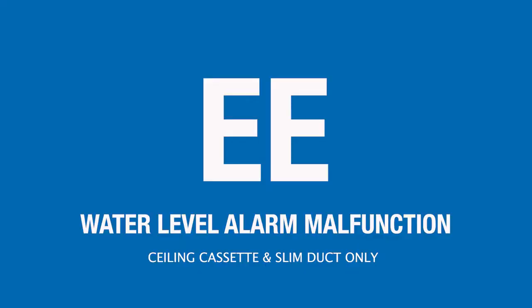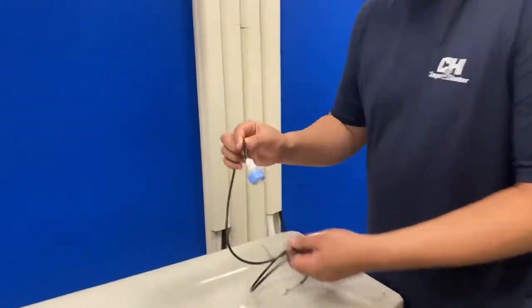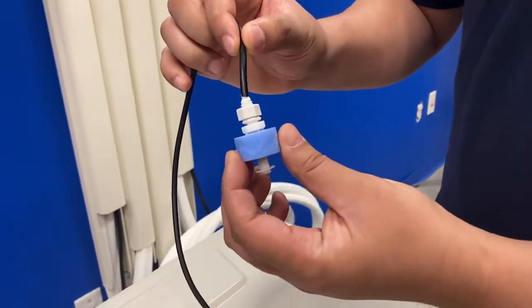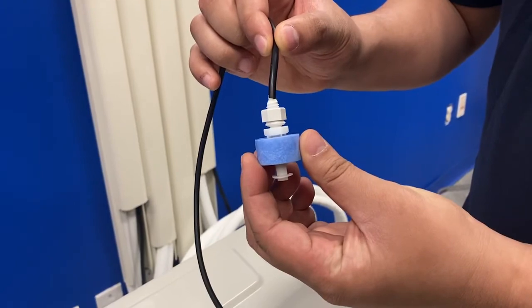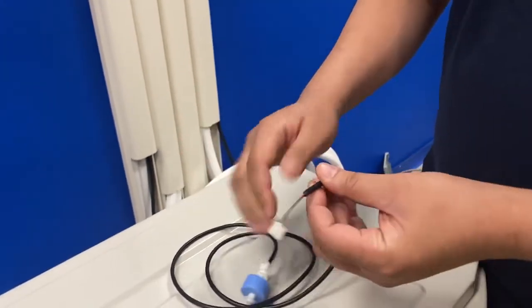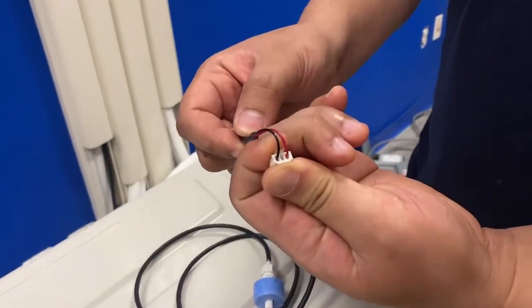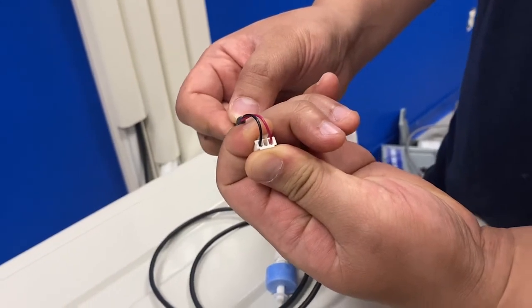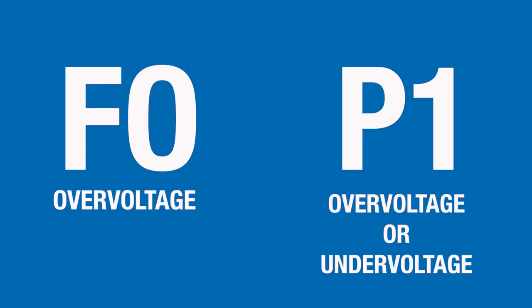If your indoor unit is displaying an EE error code, that indicates a water level float switch malfunction. First, I would make sure your drain hose is not clogged. Then I would make sure that the float switch is not jammed in an upright position. If none of these are the case, then I will just check continuity. If there is continuity, that's good. If there's no continuity, that's bad.